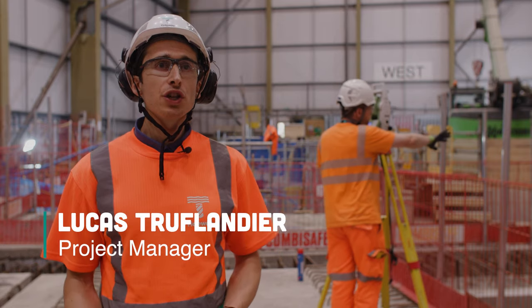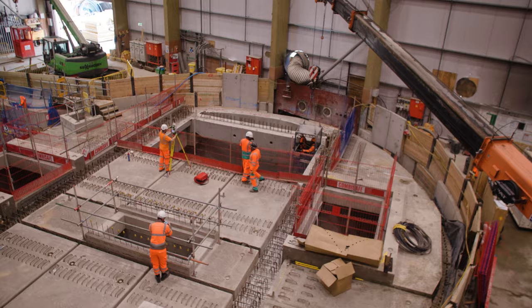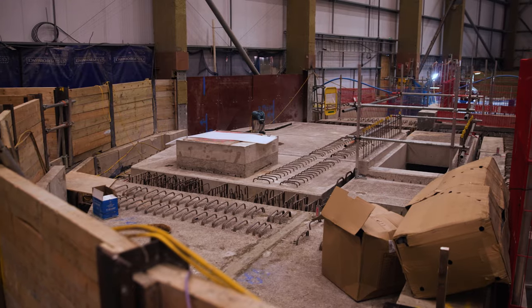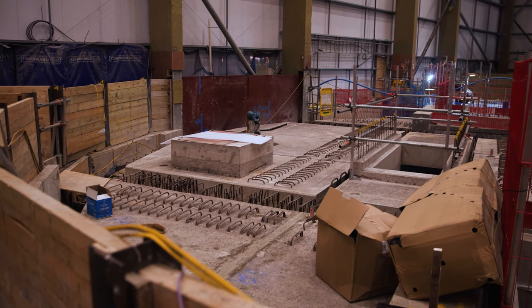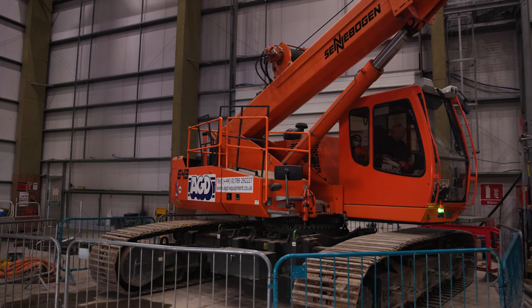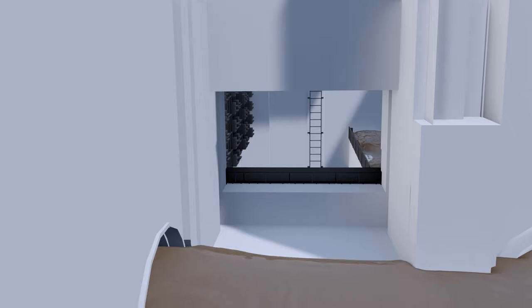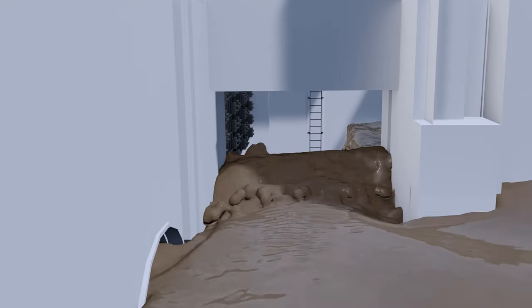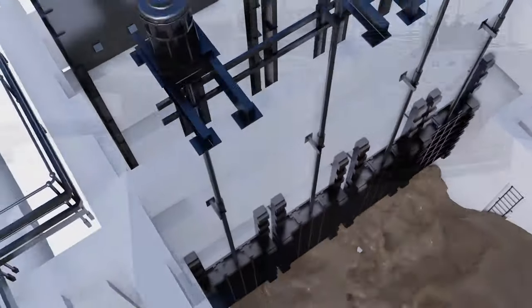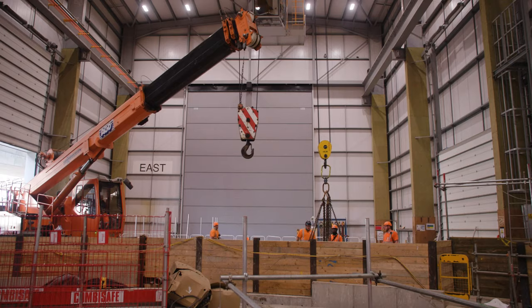So Greenwich Pumping Station is one of the sites of the Tideway overall project. It is the highest point of the Greenwich connection tunnel. It intercepts the East Greenwich relief sewer, which is one of the hubs in terms of sewer in southeast London. So it intercepts that major sewer connection via a CSO interception chamber. It intercepts the flow, redirects it into a connection culvert, into a vortex generator that is installed within the shaft before being redirected to the Greenwich collection tunnel.